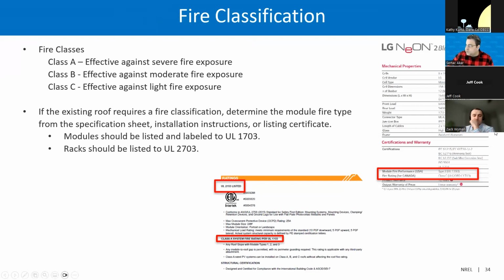And this is basically in the label of the modules. You can see the listing here, the UL 2703 listing, or the fire type listing, class C or class A. So if the existing roof requires a fire classification, the module fire type should be checked in the plan review.